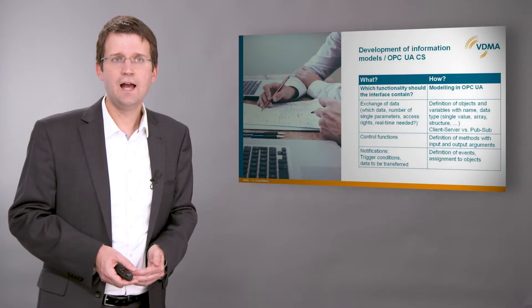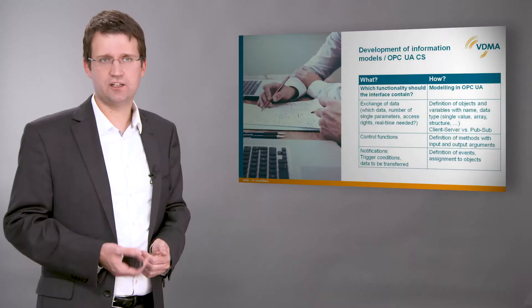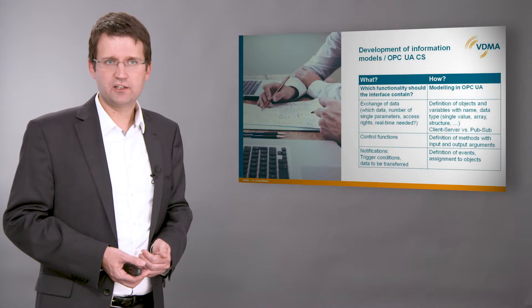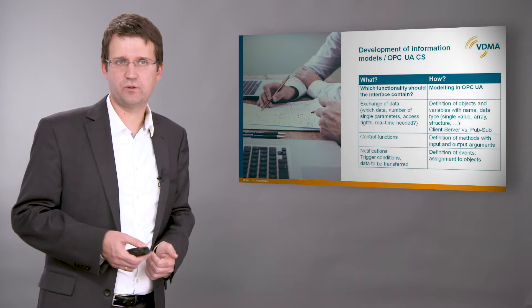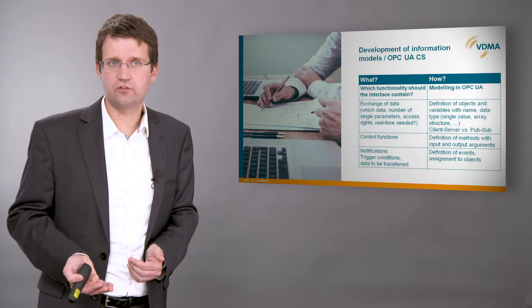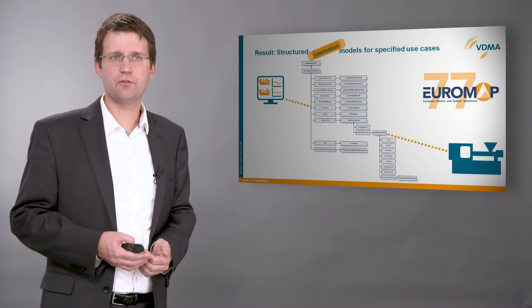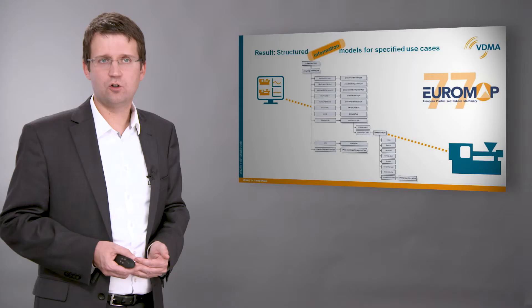How does the work in the working groups look? We have two aspects: the what and the how. Independent from the used communication technology, the functionality of an interface must be defined. This includes relevant properties of the described devices, process parameters, remote control functions, and also notifications. When this is fixed, the modeling in OPC UA starts. There, object types, data types, methods, and events are created. The result of the work is a structured model for the specific use case. By providing a semantic description, this is not only a data model, but an information model.